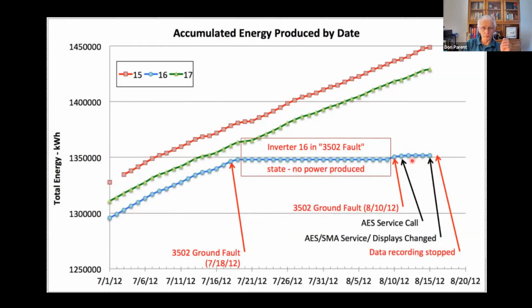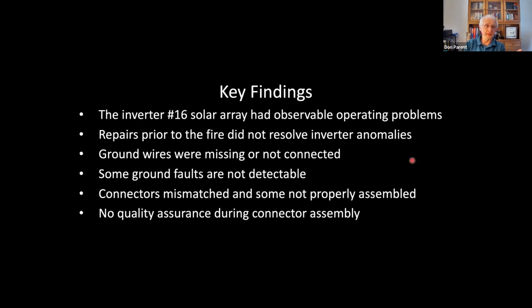So our conclusion from that is that we can't really say this is exactly what happened, because we don't actually have the evidence because it got destroyed in the fire. But there's a lot of circumstantial evidence indicating that there were observable operating problems on the roof, that prior repairs that were made to try to get the inverter up and running again were not sufficiently thorough to identify all the anomalies. There were missing ground wires. I didn't point that out earlier.